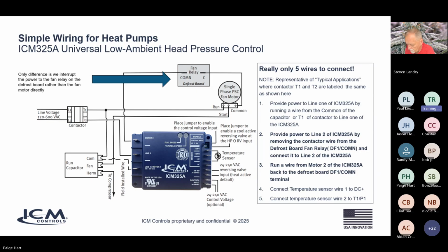The only other connection that you have to be concerned with is the HPORV jumper and the reversing valve input, HPRV input. So on a heat pump, you have a reversing valve. Now that reversing valve can be either heat active or it can be cool active. Now our device is preset for heat active reversing valves. So a lot of your typical heat pumps are cool active. So with cool active reversing valves, what you're going to do is just simply put a jumper at HPORV, which O stands for the cooling active reversing valve.